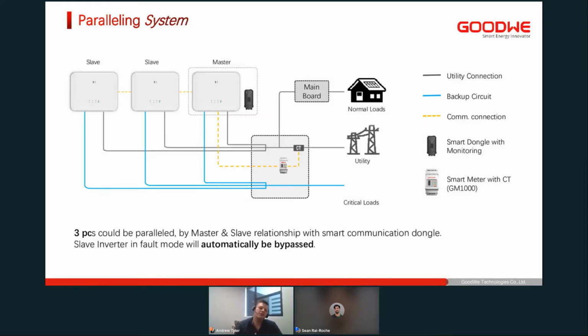Typically, how this would be done is you've got a master device that is controlling the entire system. Your energy meter and your CT clamp, as well as your smart communication dongle, are connected to the master, and then your slave inverters are connected to the master via RS485. Three pieces could be paralleled, so you can build up to a system of 18 kilowatt with our 6 kilowatt, or obviously slightly smaller if you look at any other of the inverters sizing. And then you'll also note that you would use a DC bus bar for your batteries, and then of course parallel the connections for the AC output as well.